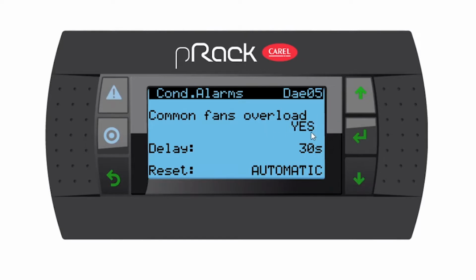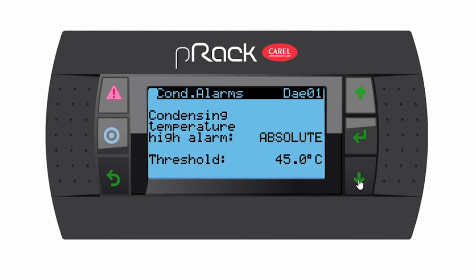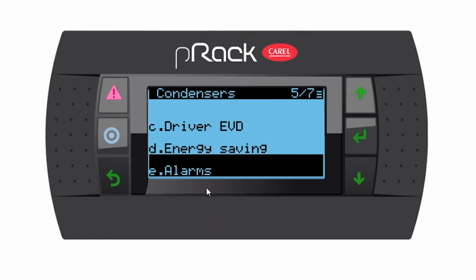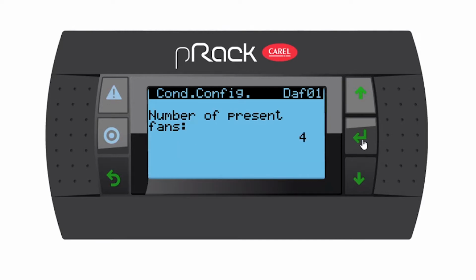Common fans overload alarm. Yes, I do have one. You've got a delay that you can set, and also a reset, automatic or manual. I'm going to leave this and go down. Condensing temperature, oh, back at the beginning. Awesome. So let's go back and let's go to F configuration menu and enter.